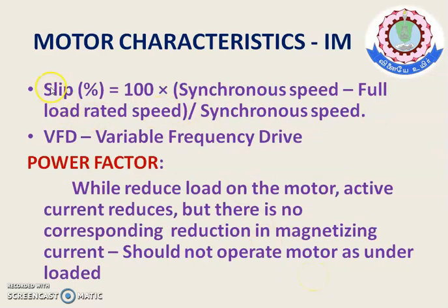Now, another terminology is slip. Slip is only for the induction motor, not for synchronous motors. Slip percentage is equal to synchronous speed minus full load rated speed, that is, the actual speed of the rotor, divided by synchronous speed, multiplied by 100.